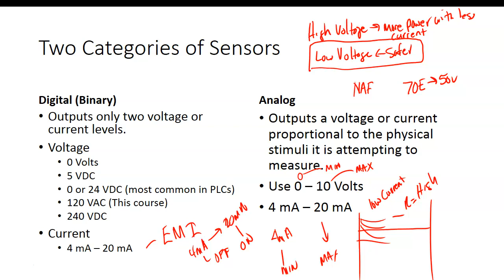With current, 4 milliamps represents the minimum value and 20 milliamps the maximum. With voltage, 0 represents minimum and 10 represents maximum. How many combinations could we have between 0 and 10? A lot, since it's essentially infinite. But then we bring that into an analog to digital converter, and how many digits you use for the binary equivalent determines how accurately it represents the signal. On the PLC's A to D, it's a 10 bit converter, which gives 1024 levels.